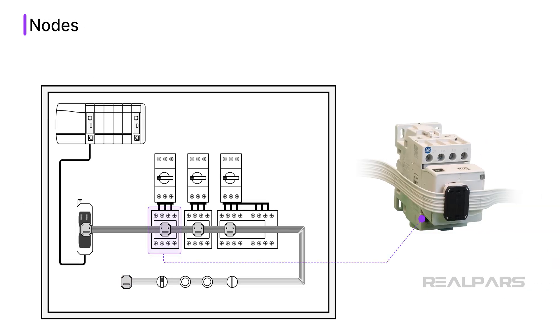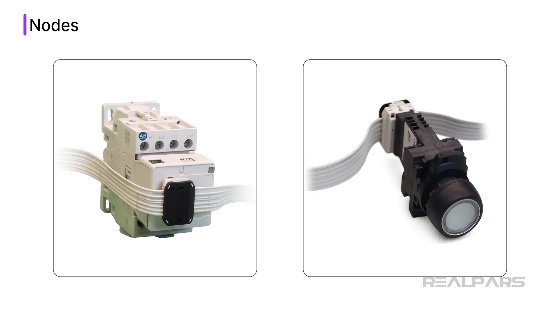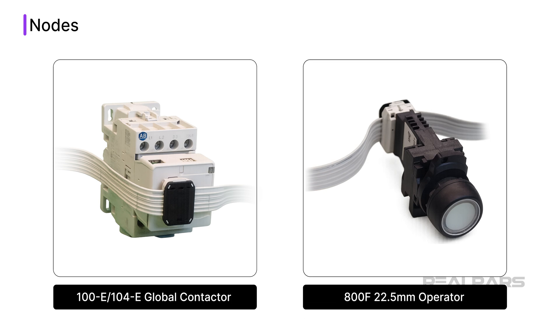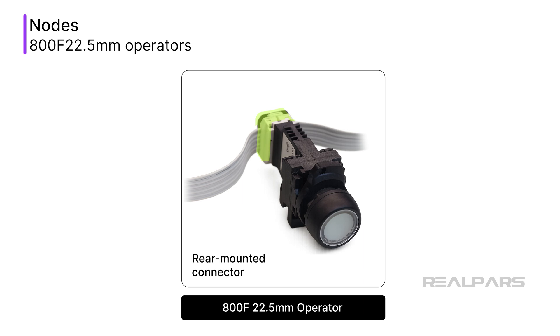Nodes are connected to the flat cable using connectors that allow quick termination with standard tools. These nodes use Physical Layer Collision Avoidance (PLCA) to determine which device can send information over the Ethernet cable. This protocol helps to ensure reliable communication between devices and the gateway. The initial launch of in-cabinet Ethernet IP supports two types of nodes: 100E and 104E global contactors, and 800F 22.5 millimeter operators. Contactors are connected to the flat cable using a front-mounted connector, with support for contactors from 9 to 96 amps with interlocking for basic motor starter control.